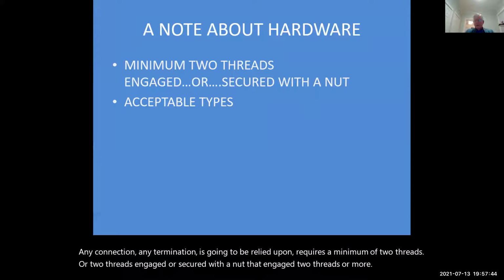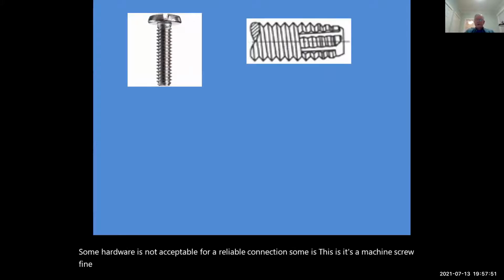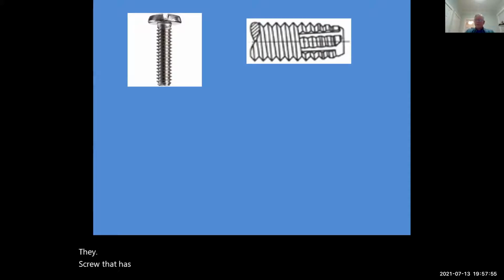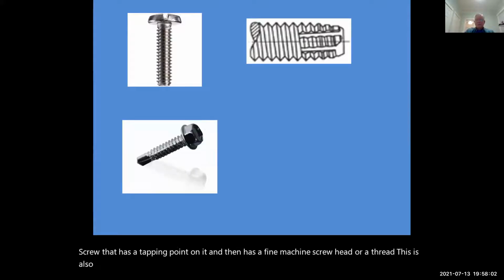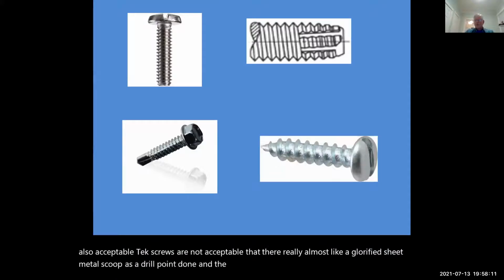Some hardware is not acceptable for a reliable connection. Some is. A machine screw, a fine thread, a screw that has a tapping point on it and then has a fine machine screw head or thread, is also acceptable. Tek screws are not acceptable. They're really almost like a glorified sheet metal screw. It has a drill point, and the sheet metal screw definitely is not considered suitable hardware for terminating grounding or bonding terminations.